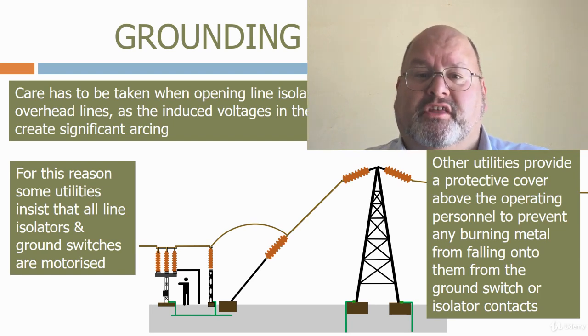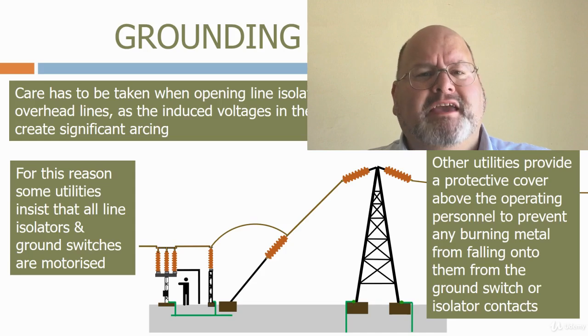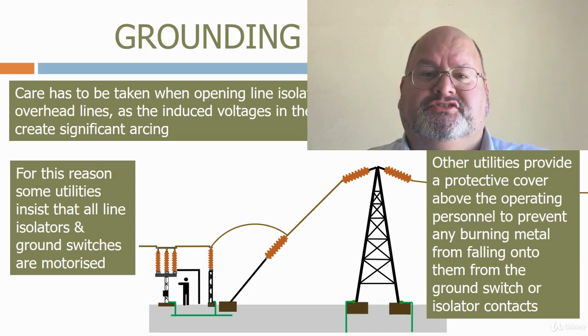Isolators can be padlocked off to ensure that the circuit is dead, but there may still be voltages and currents induced onto the circuit from an adjacent circuit. Providing ground switches ensures that these are neutralized and that the personnel working on the equipment under maintenance are fully protected.